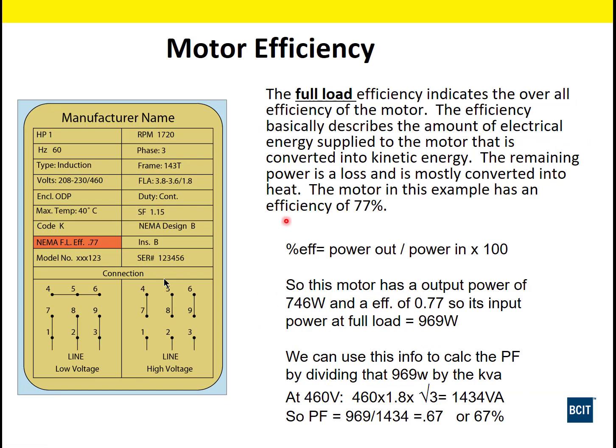Okay, efficiency. We all know what this is. Efficiency of the motor. It's the relationship of power in to power out. So the power into the motor is going to be our watts. And if it's a 77% efficient motor, I did the math here for this one. That means our input power to get that full 1 horsepower of power out is 746 watts. 1 horsepower is 746 watts. At 0.77 efficiency, we're going to have to push 969 watts of power into that motor. So the difference is our lost energy.